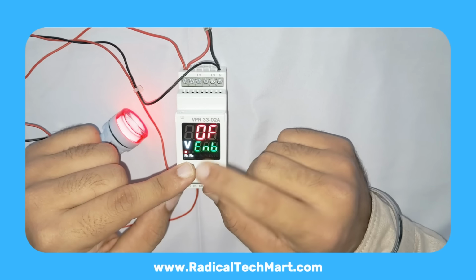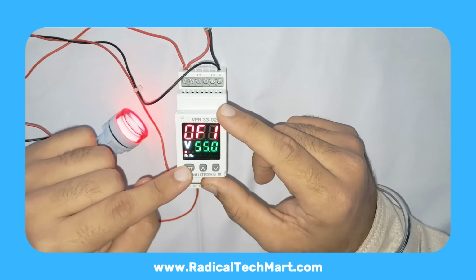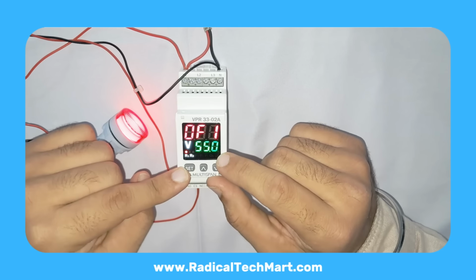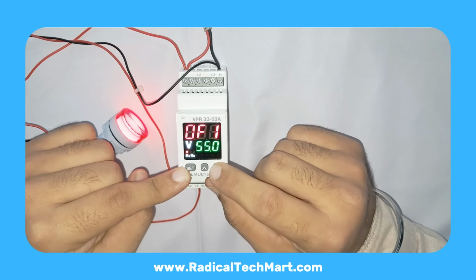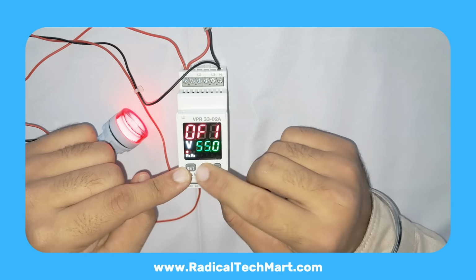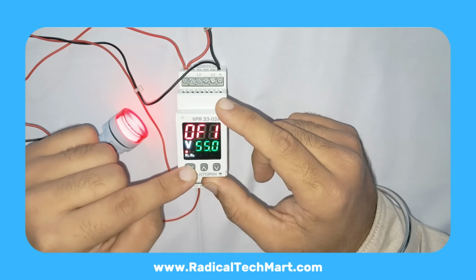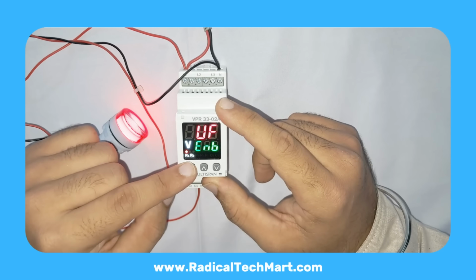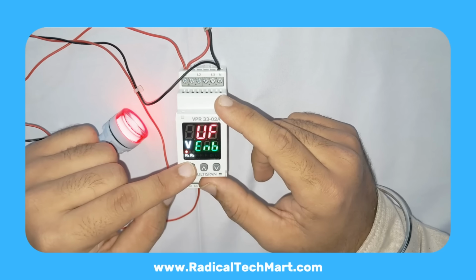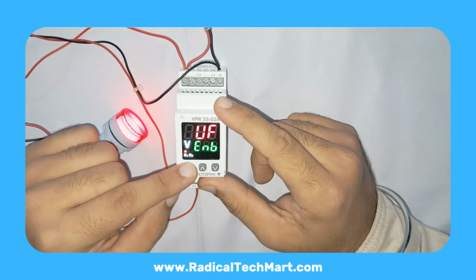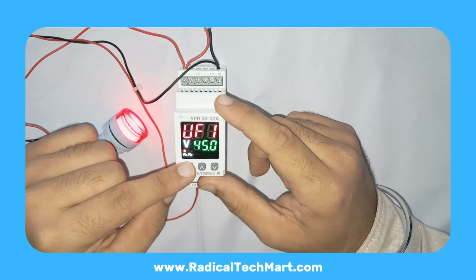Enable or disable using up-down. Press Set. The default overfrequency setpoint is 55 Hz, which you can adjust as per your requirement. Press Set again. You will now see UF, under frequency. Again, you can enable or disable. Press Set. Here you can set the under frequency level.